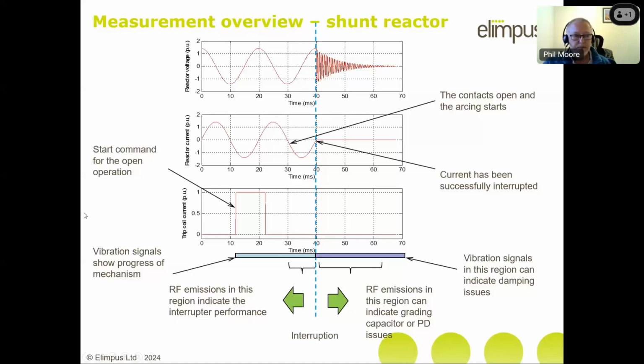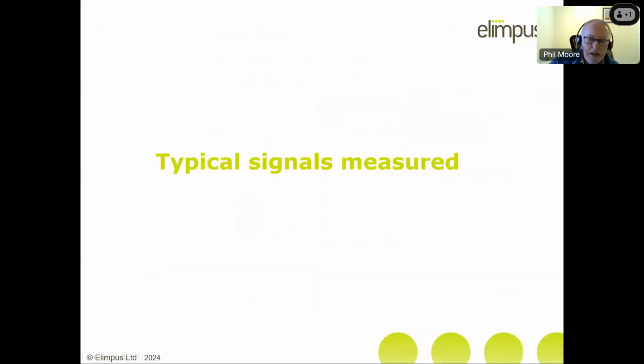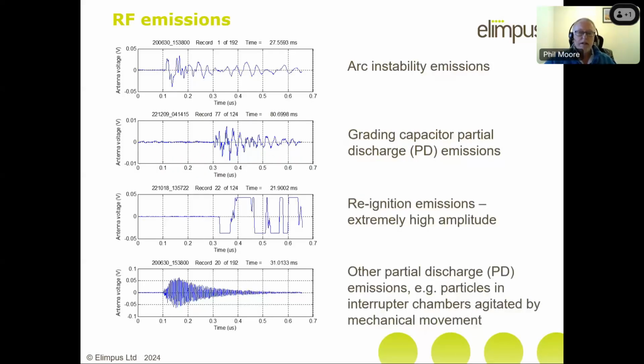I'm going to show you some typical signals now, just in isolation, to explain what you would see when you take a measurement from a breaker opening a shunt reactor. It could be opening or closing. Opening is by far the hardest thing to do. These show typical signals from the RF side of the device, and there are essentially four separate things that we see.